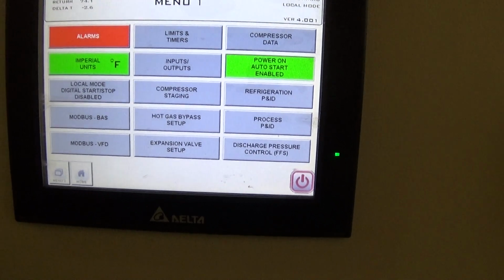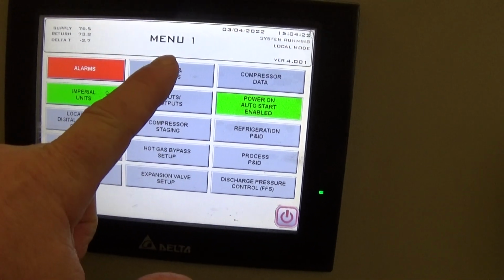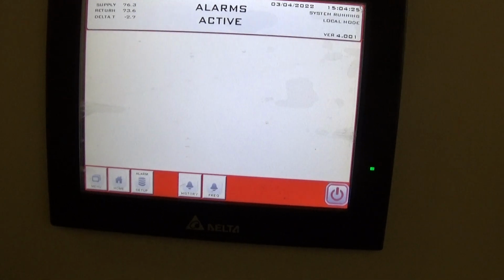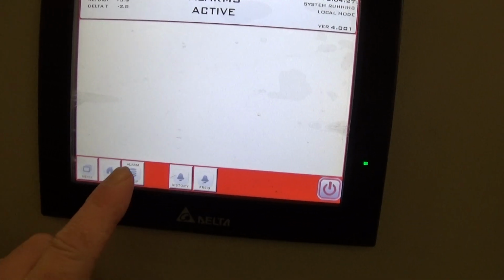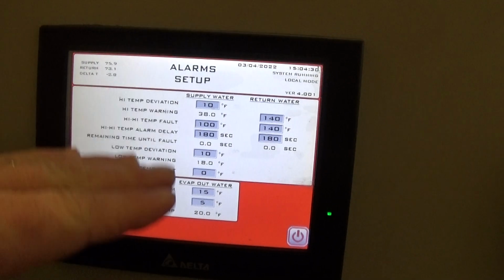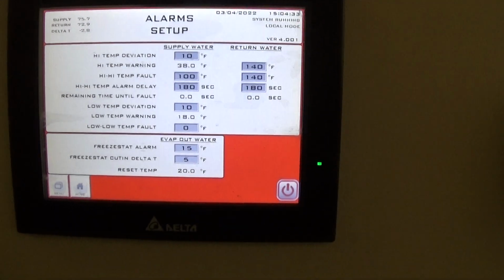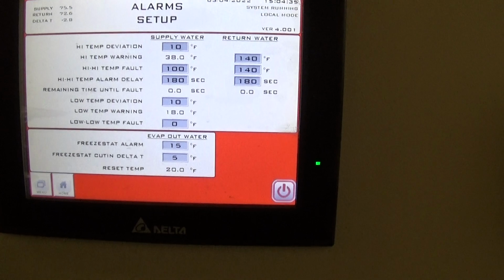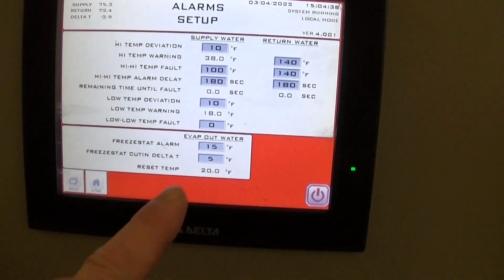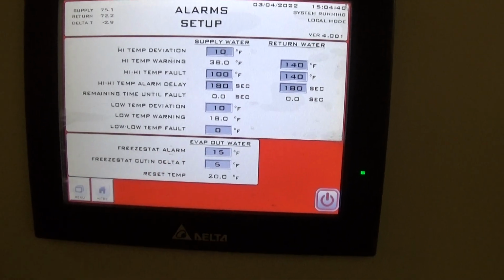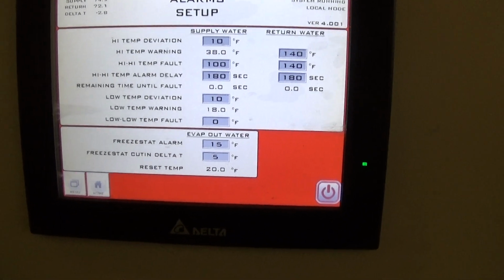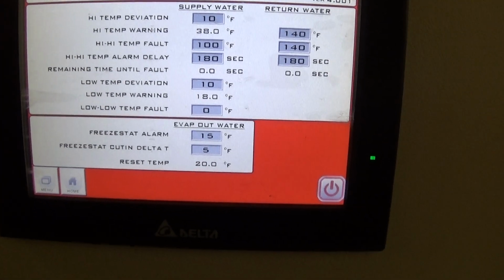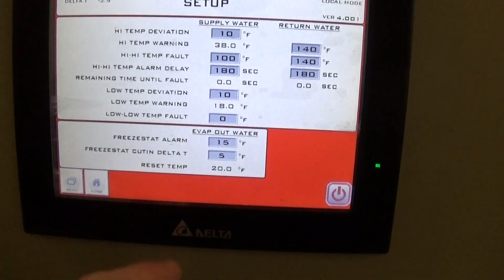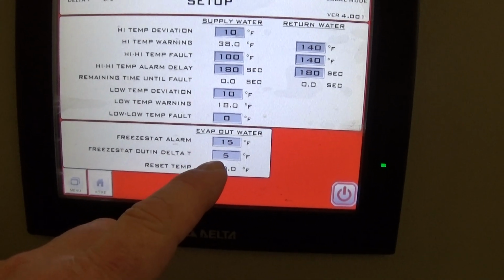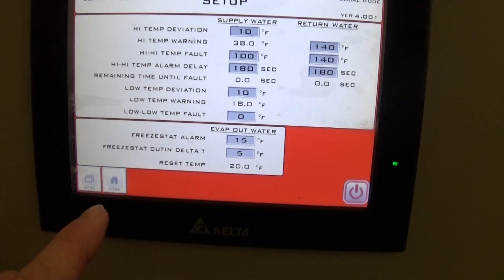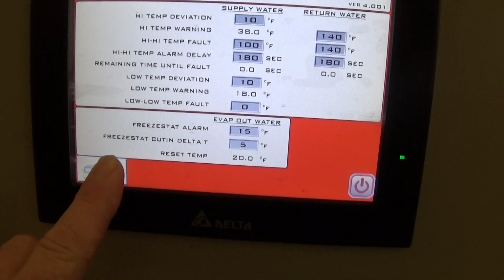Sorry about that. We're going back to our main menu here. We can go into alarms, alarm history, alarm setup. This gives you different type of parameters as far as over temperature, under temperature, and deviation. Probably won't have to mess with that. We got our freeze stat alarm. If the glycol were to get down to 15, that's really not appropriate. An alarm will go off, and then the alarm would reset itself once we get 5 degrees above that parameter. Go back to our home screen here.